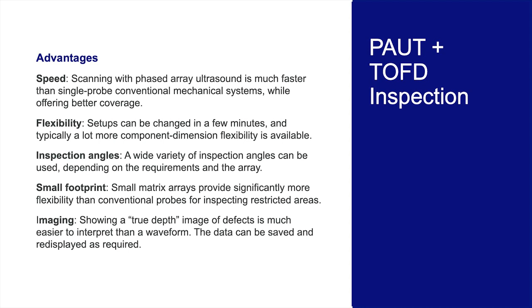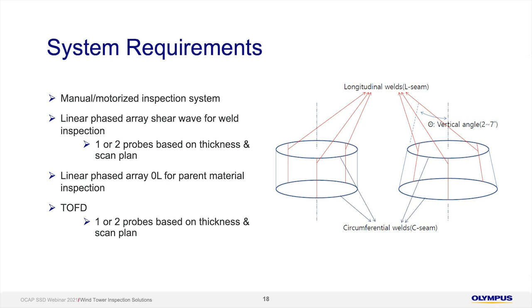Okay, next we're going to talk about what Olympus offers. First of all, what are the typical system requirements? It can be either manual or motorized inspection systems. We also need a linear phase array shear wave probe for the weld inspection. You might need more than one or two probes based on the thickness and the scan plan, of course. And you probably also need a 0 degree probe for the parent material inspection. And you can also include TOFD, and depending on the thickness again, you might need one or two probe sets.